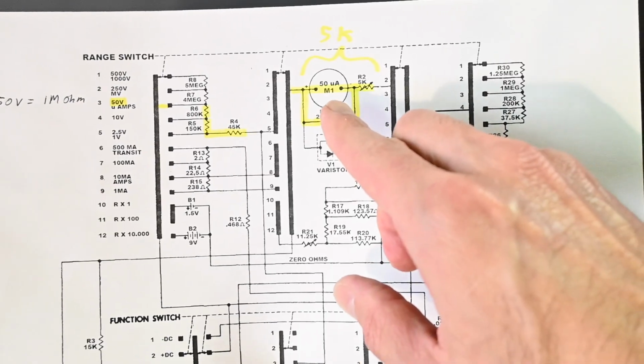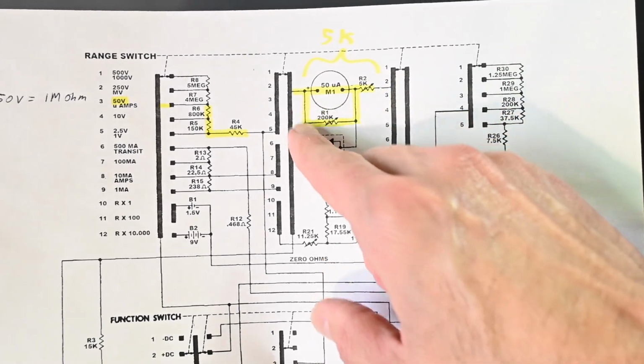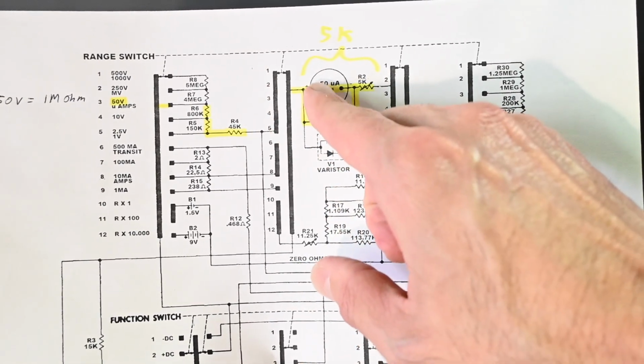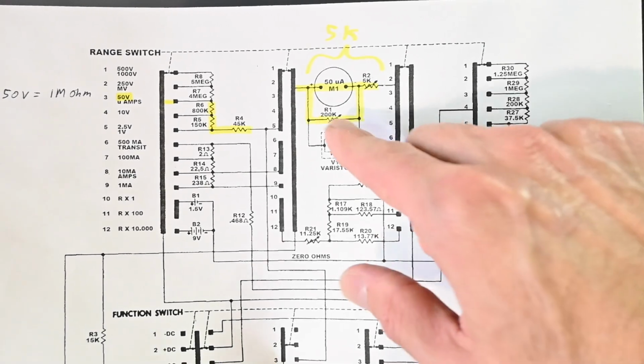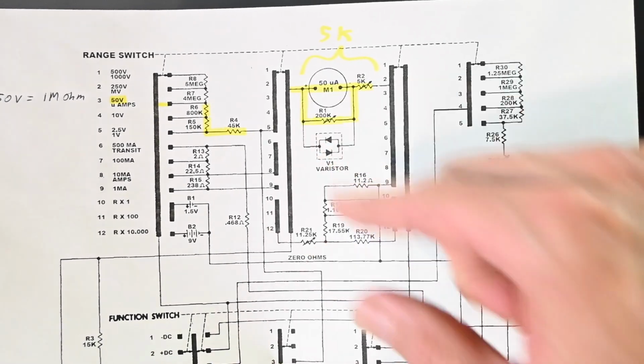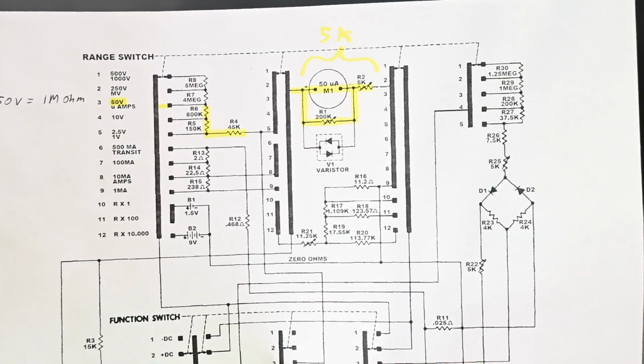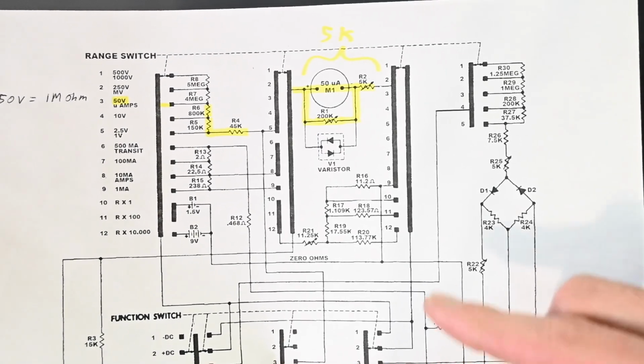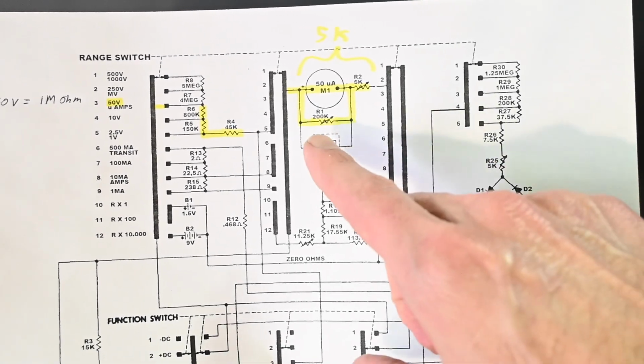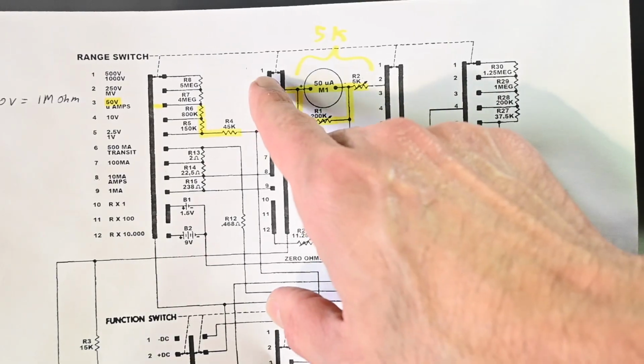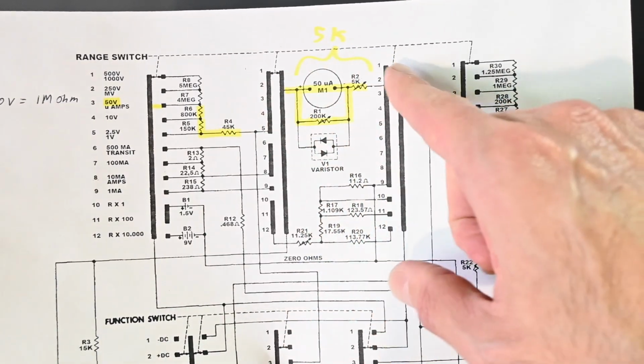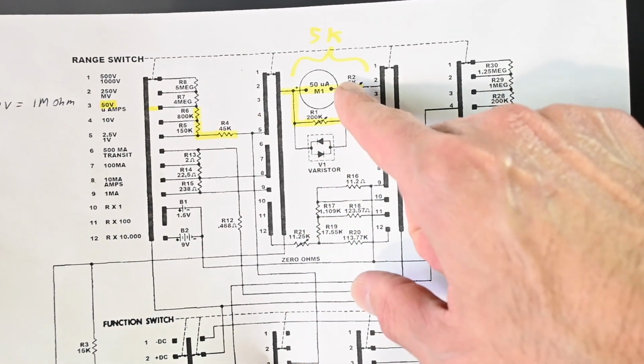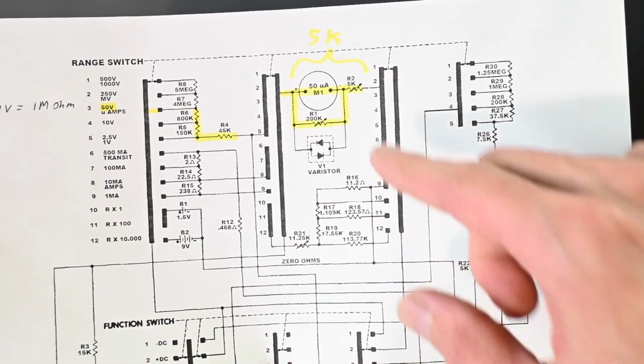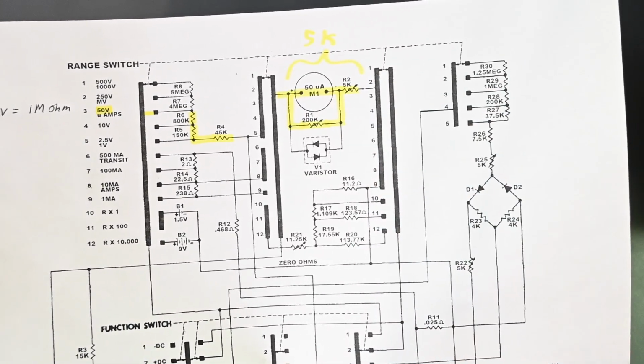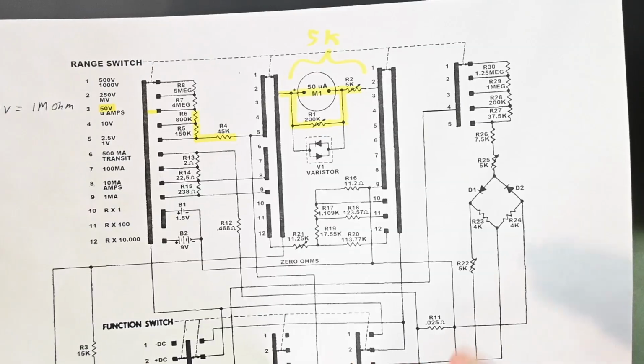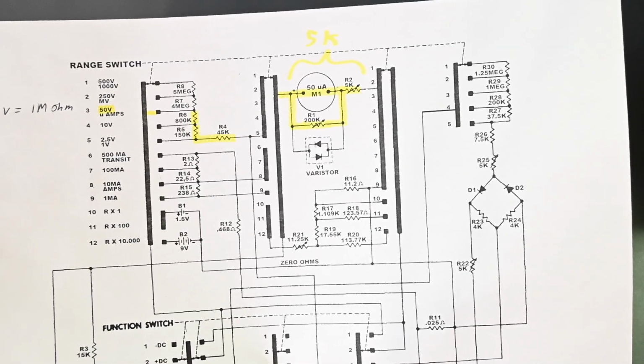So again, we already saw that 50 microamps without anything else connected to the meter will make it go beyond that tick mark. So we're going to adjust this potentiometer so that we get right on that first tick mark on the right hand side. Then the second step is to connect 250 millivolts across the meter from this side all the way over to this side. So now this 5K potentiometer is in the circuit, and adjust the 5K potentiometer so that we get full scale indication, which is 250 millivolts.